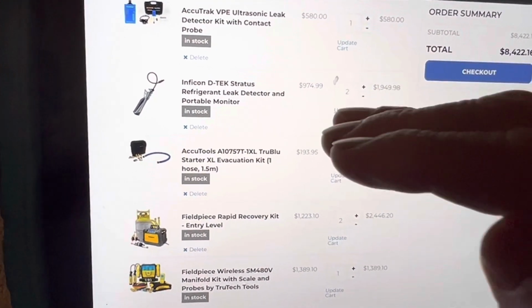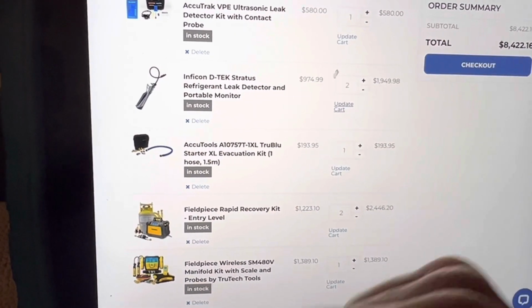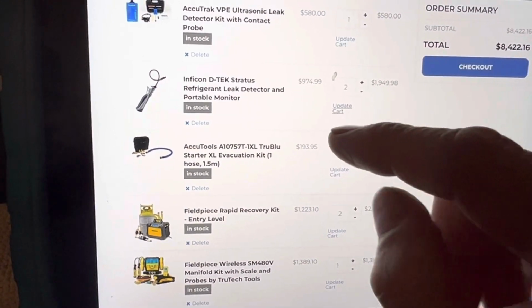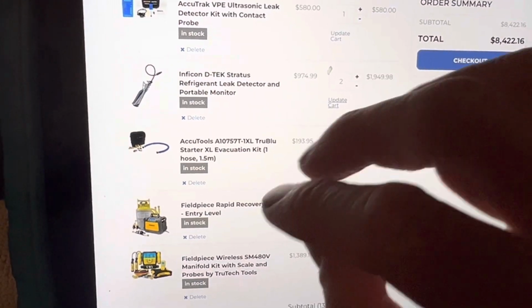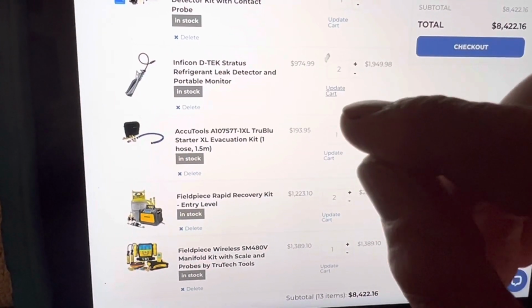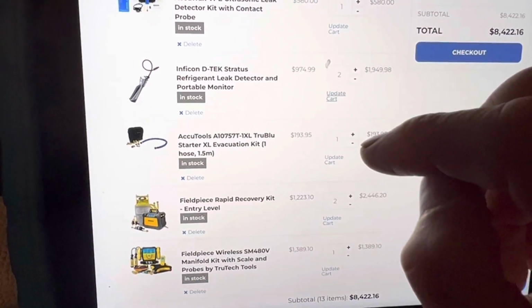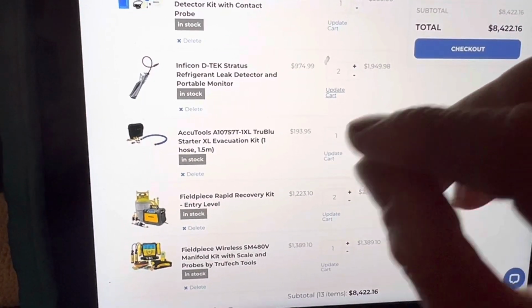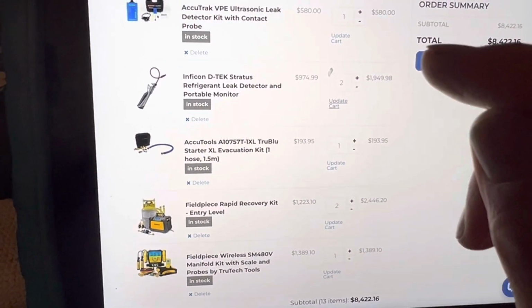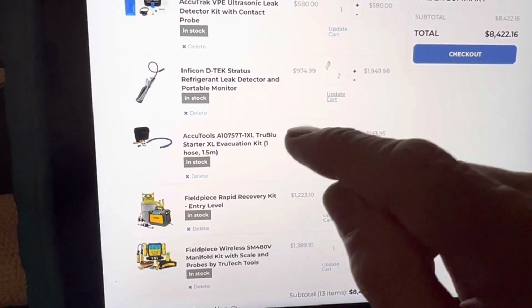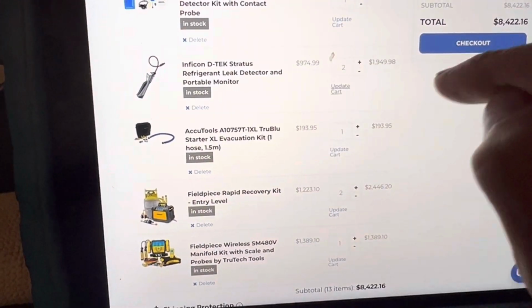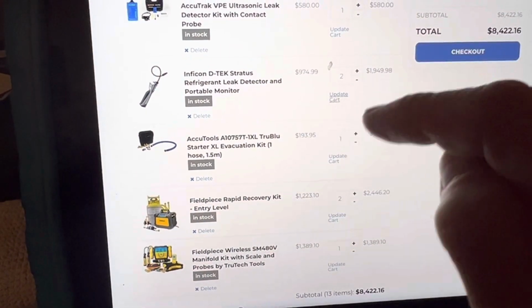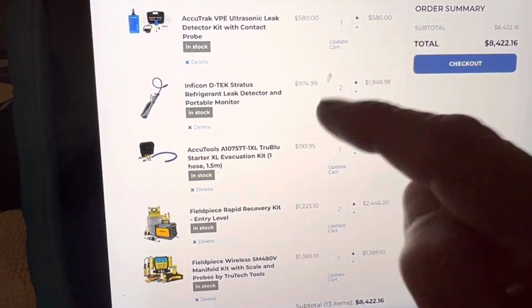That would be my minimum leak detector to go to, but it's more difficult to use. It's a little touchy-feely — some guys who don't understand it well get upset and frustrated because they don't know how to use it right. Using a heated diode leak detector is different from using an infrared leak detector, and if you don't know the differences, you will not be happy.